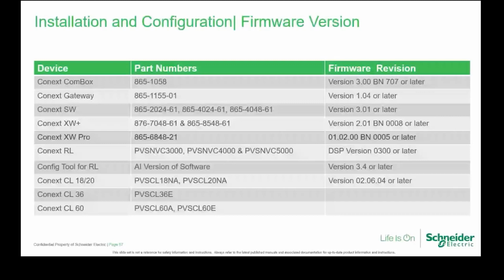We're also going to make sure that you install the latest version of the firmware on this. It's just an example. For the Combox, Gateway, SW, XW Plus, XW Pro, all those firmwares are available from our website. You can download and install them onto those devices by using the Conext Gateway, the Combox, or a configuration tool. The other ones are just our legacy inverters, where you need to make sure you've got the right firmware that matches up with the XW Plus for frequency shift.